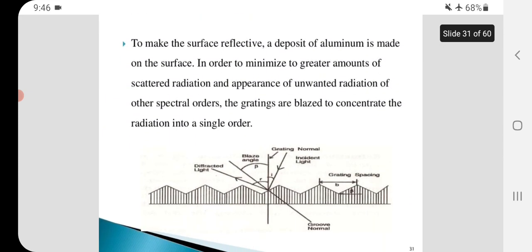To make the surface reflective, a deposit of aluminum is made on the surface. In order to minimize greater amounts of scattered radiation and appearance of unwanted radiation in other spectral orders, the gratings are blazed to concentrate the radiation into a single order.